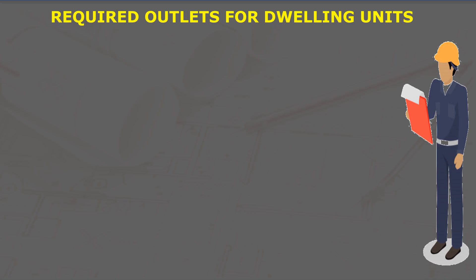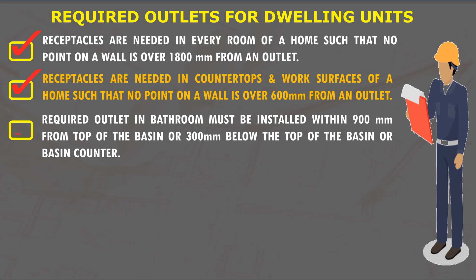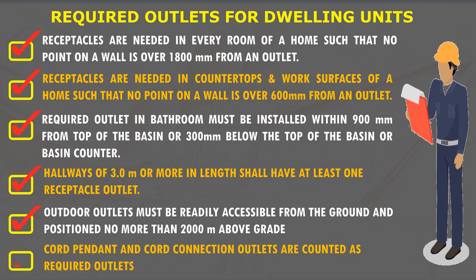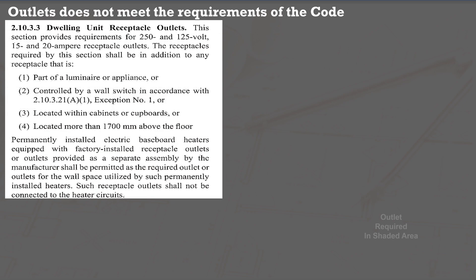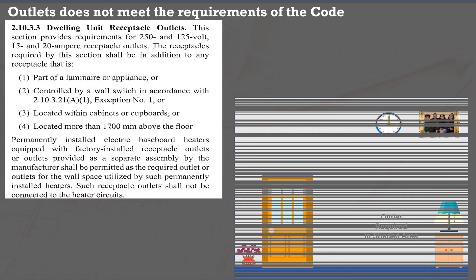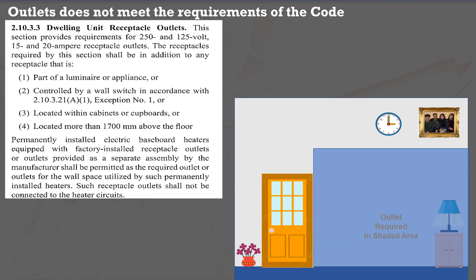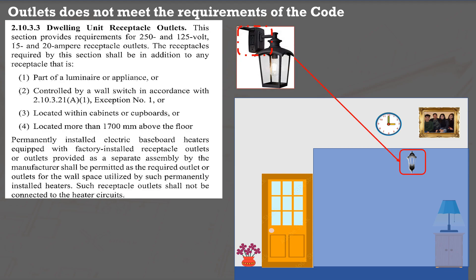We have now identified which areas of dwelling units the code requires an outlet. We also learned which type of outlet installation is considered compliant with the required outlets as specified in subsections 2.10.3.1a and b. What about an outlet installation that does not meet the receptacle outlet spacing requirement? We can find that in subsection 2.10.3.3. For example, if an outlet is required in a certain area but the installed outlet is part of a luminaire or appliance, as stated in bullet number 1, this outlet does not meet the requirements and an additional outlet must be provided.